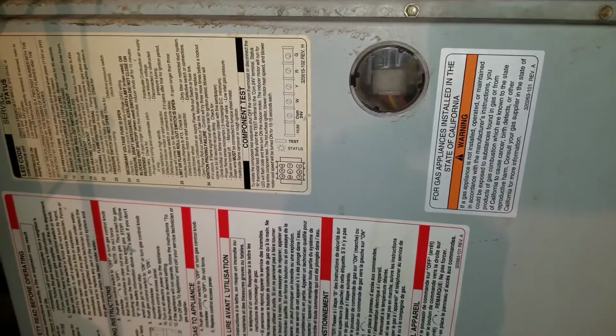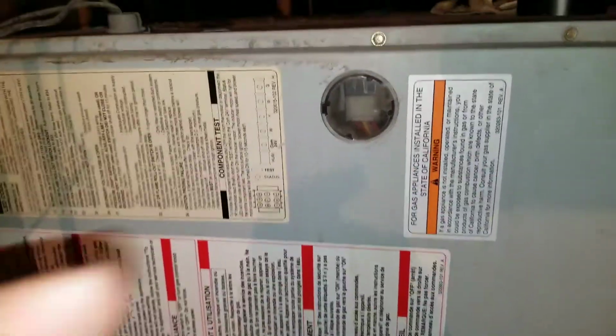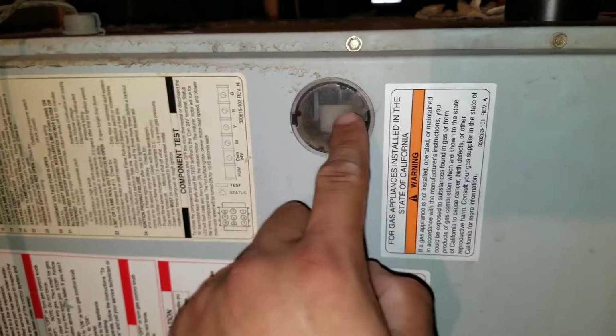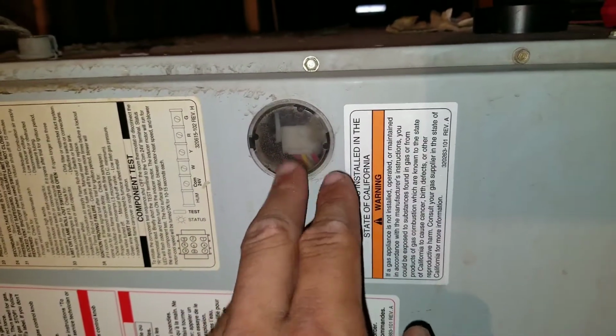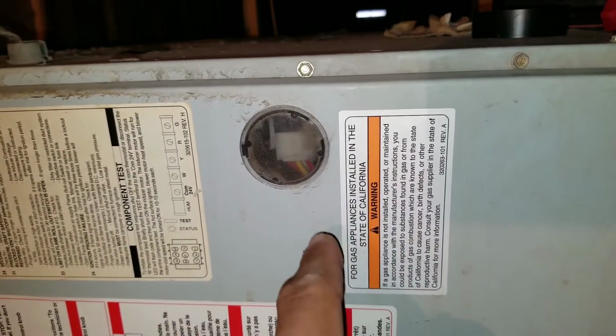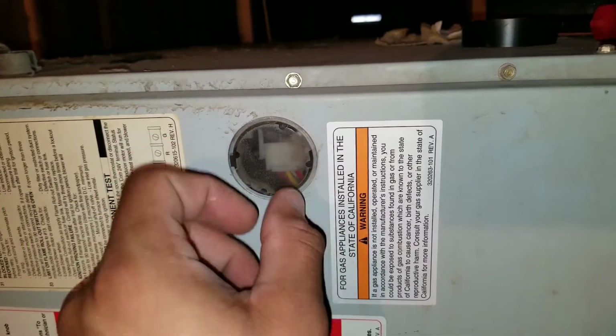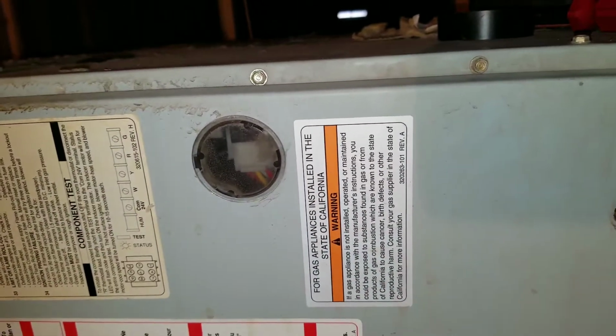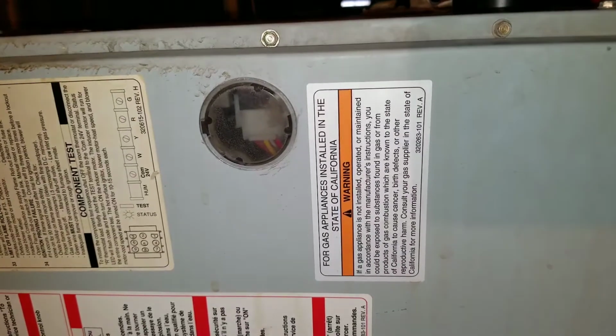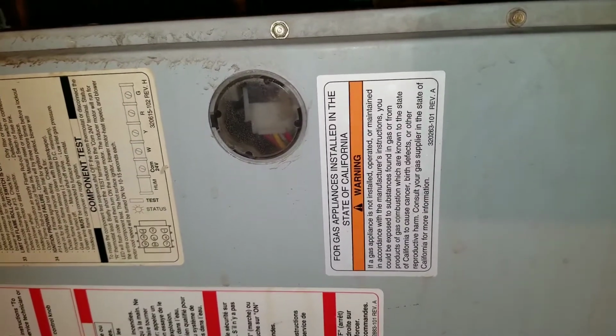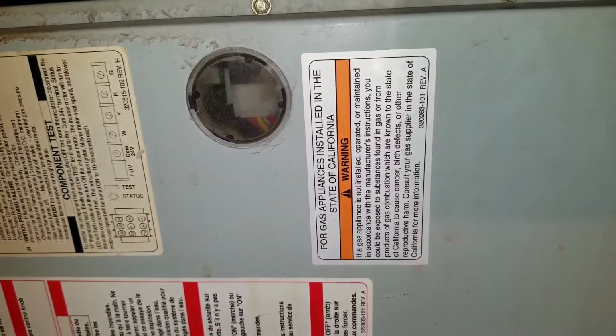So here I'm at my furnace. My board's going to be inside. Here we have a little sight glass. This is going to allow us to look at the actual LED light that turns on and off. And so basically when you look on there, you should be able to determine what codes or what faults are coming up on the furnace board.